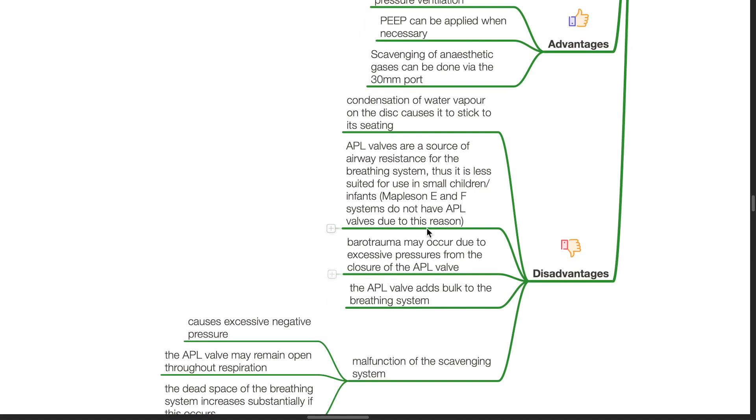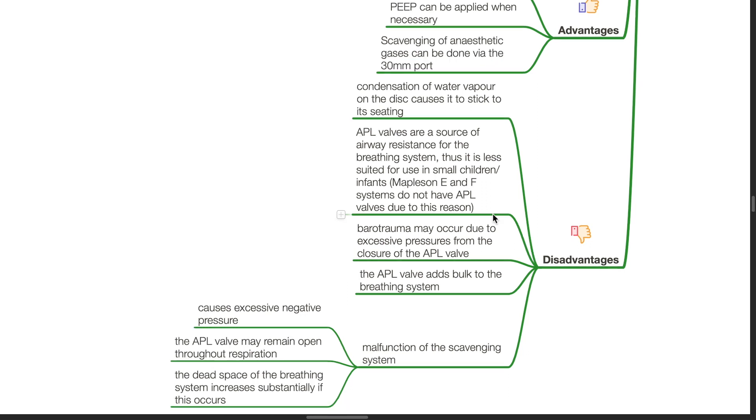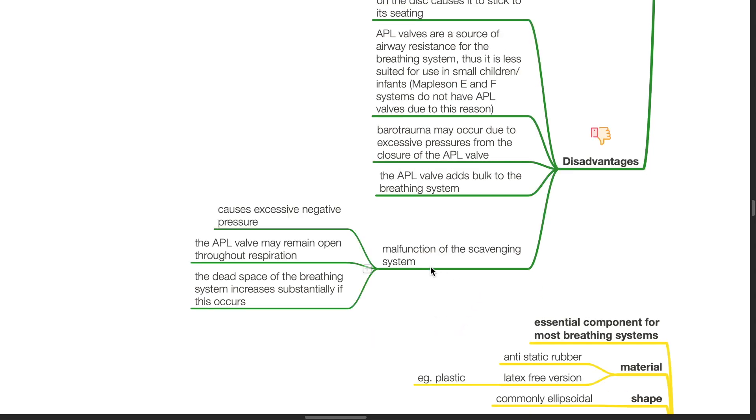Disadvantages. Condensation of water vapour on the disc causes it to stick to its seating. APL valves are a source of airway resistance for the breathing system. Thus it is less suited for use in small children or infants. Mapleson E and F systems do not have APL valves due to this reason. Barotrauma may occur due to excessive pressures from the closure of the APL valve. The APL valve adds bulk to the breathing system. Malfunction of the scavenging system causes excessive negative pressure. The APL valve may remain open throughout respiration. The dead space of the breathing system increases substantially if this occurs.